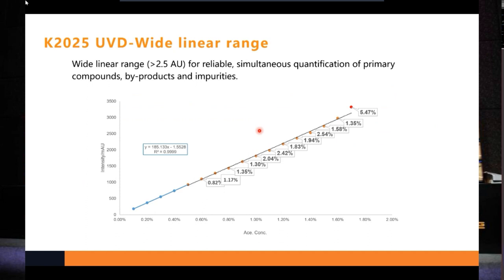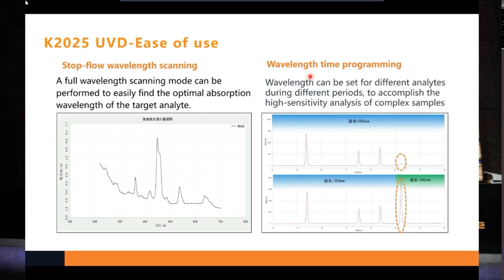So wide linear range can be useful when low concentration and high concentration of components are both included in one sample. That's when the wide linear range makes sense. And the UV detector also has stop-flow wavelength scanning and wavelength time programming functions. When we don't have the spectral information of the compound, we can use the wavelength scanning. The scanning is very useful for us to find the optimal absorbance of the specific analyte.